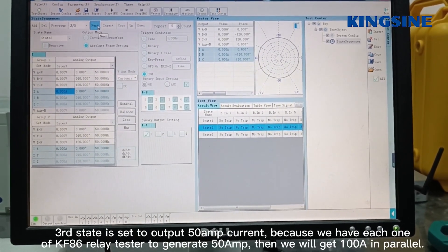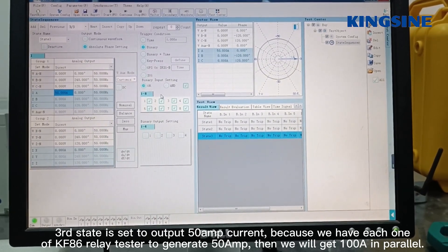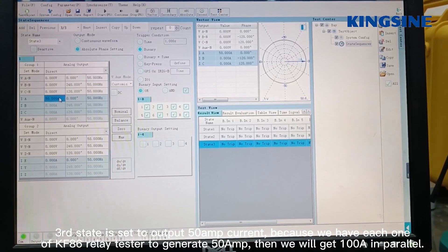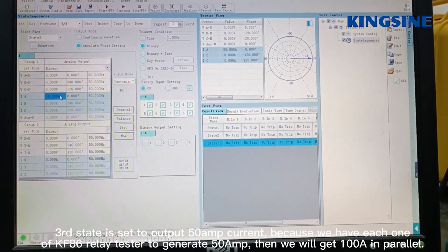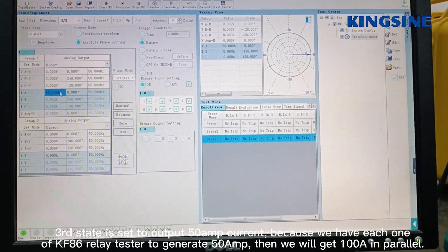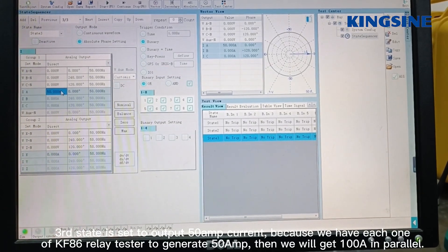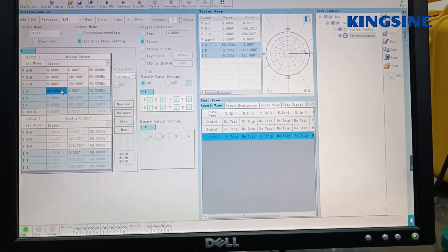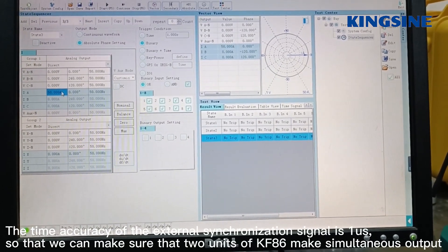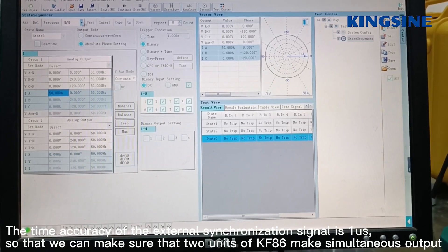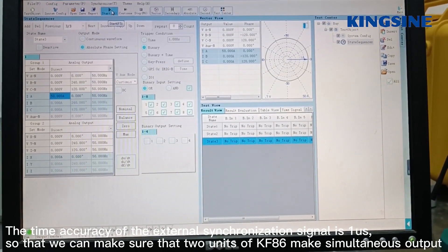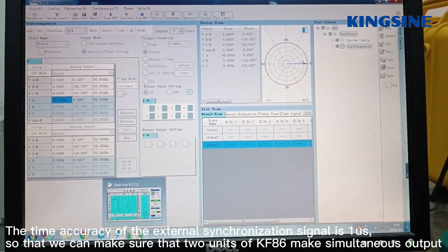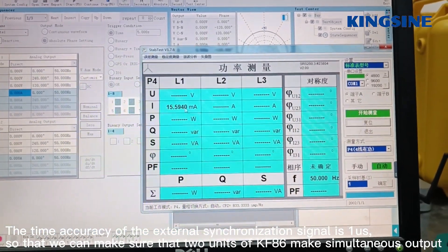The third state is set to output 50 amp current. Each one of the KF86 testers will generate 50Amp, so we will get 100A in parallel. The time accuracy of the external synchronization signal is 1 microsecond, so we can make sure that the two units of KF86 make simultaneous output.